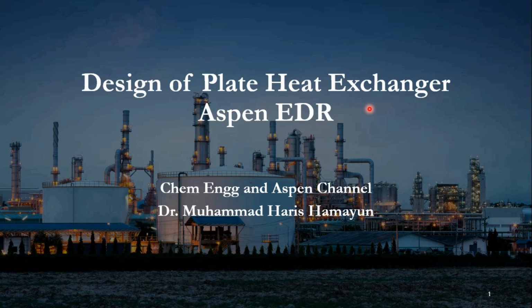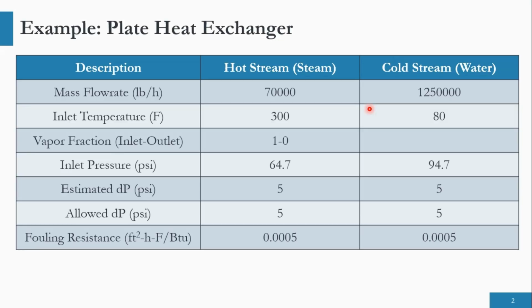So coming to today's activity, the statement is that we have been given a steam water system. The steam is a hot stream, so it will be cooled down in the system, while the cold stream is water that will be heated in the process. The mass flow rate of the hot stream is 70,000 pounds per hour, while that of the cold stream is 125,000 pounds per hour. The inlet temperature of the hot stream, which is steam, is 300 degrees Fahrenheit, while that of the cold stream, which is water, is 80 degrees Fahrenheit.